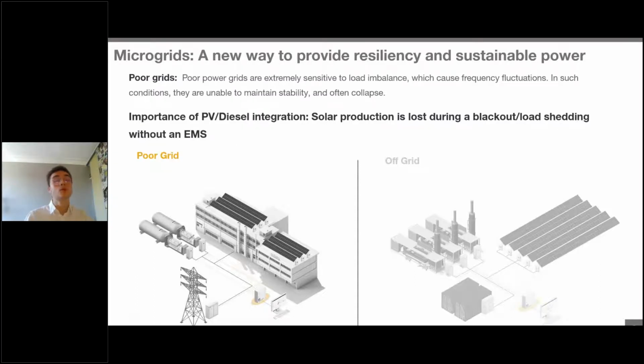So we can start with the on-grid system setup. We basically have two different system setups, the on-grid setup and the off-grid setup. The on-grid setup is a system where most of the time you have the public utility being the mains, but we have this grid that is very sensitive to load imbalance with a lot of frequency fluctuation, and it happens that the grid fails. So when the grid fails, you have those gensets that automatically turn on to ensure that we still have some energy being produced on site, so that the commercial and industrial activities, for example, can continue. If you don't have any PV-genset controller installed on site during blackouts and when the gensets are turned on, you won't be able to produce energy with the inverters.